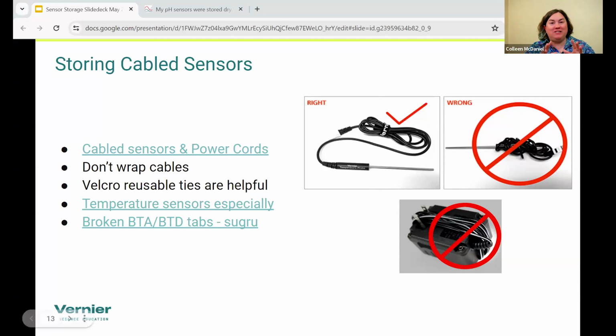The number one sensor we see this happen on is our temperature sensors, and CO2 sensors would be number two. The way you can tell if it's a wire breakage is you move the sensor and the readings will go all over the place. So that's something to keep in mind, especially with those sensors.